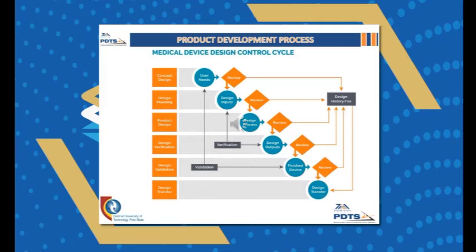Working with design control is an effective way of designing a medical device that is safe and meets the customer needs. That starting point with medical device development process is intended use. It is important to get the intended use right. It is a description of user profile, indications of what the device is intended for, patient group, and other relevant conditions of use as intended by the developer. One way of coming up with intended use is asking questions such as who will use the device, on whom will the device be used, what will the device be used for, when and where.